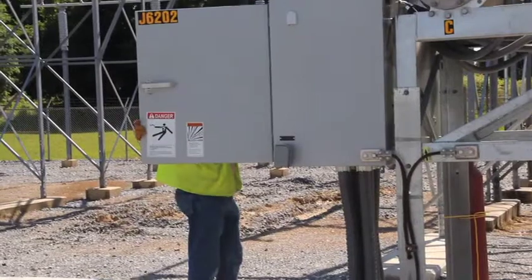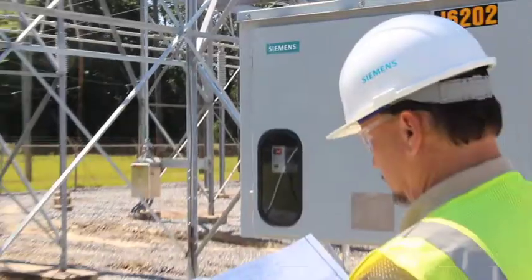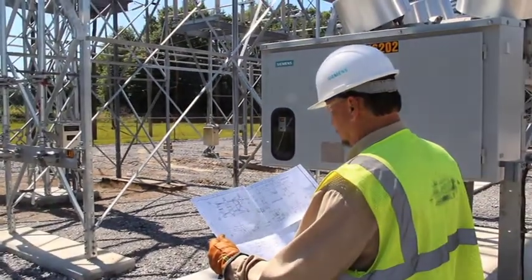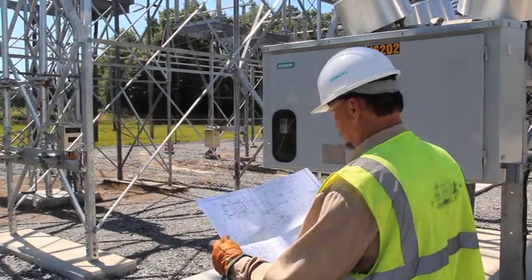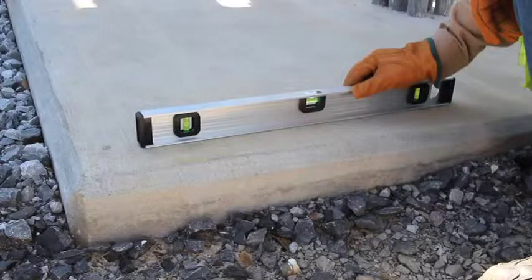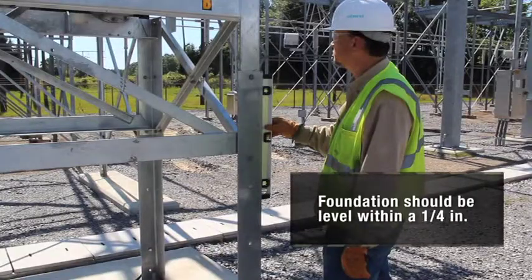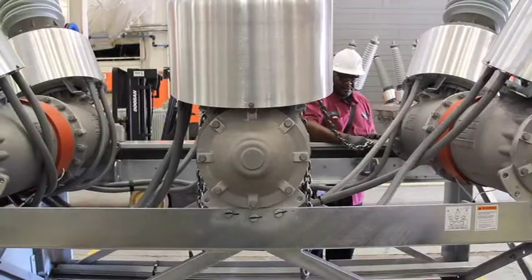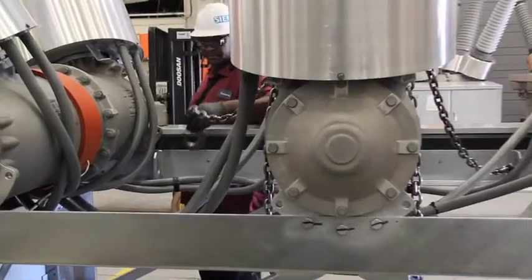circuit breaker. These are not part of the installation kit provided by Siemens. The breaker should be installed with sufficient space for cleaning, inspecting, opening doors, and removing the interrupters. Refer to the outline drawing located in the pocket of the mechanism cabinet door. The foundation should be prepared before the breaker arrives and should be level within 1/4 inch of the 4 stud locations. The breaker must be lifted in order to attach the 4 legs.